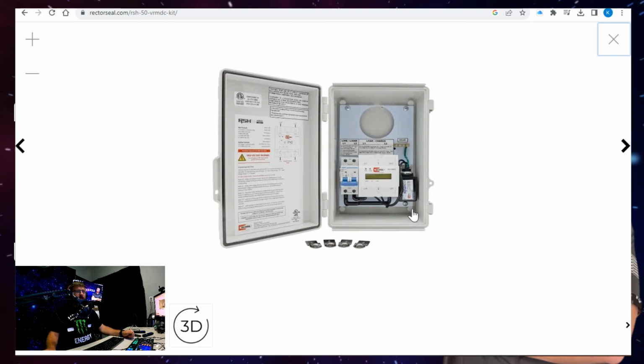And they're pretty nice. I tested them out. I wouldn't say this would replace disconnects for every piece of unit, but I would say this replaces disconnects for inverter systems. I would rather use this than a normal disconnect, because then you can have everything all there: your disconnect, your voltage monitor, and your surge protector. And then you can go ahead and throw a surge protector at the air handler to protect it on top of that, because what's the number one failure on these things? The boards, and that's all they are, is just boards.